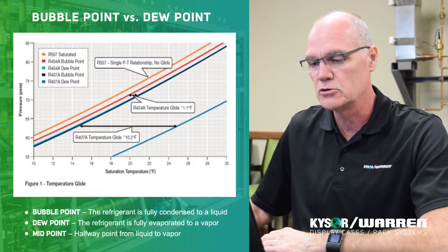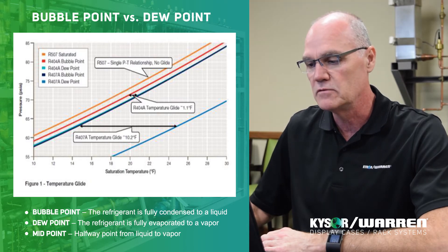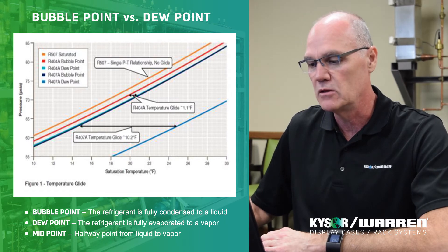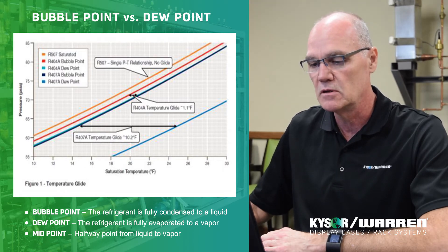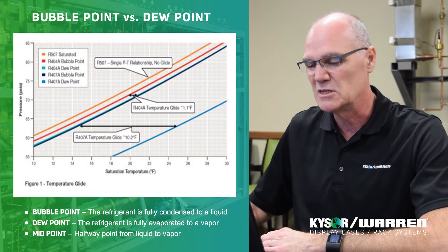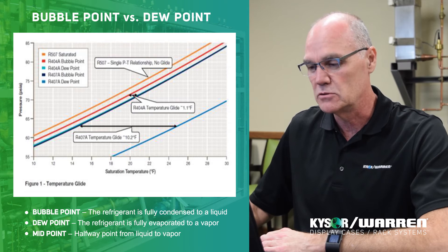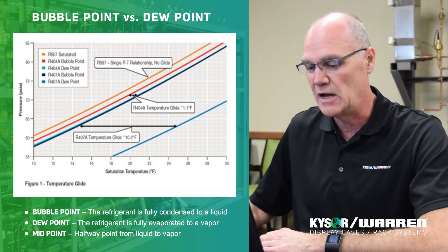If you look at the chart on the screen, the graph shows 507 and 404A, and there's one line that represents each one of those. So if I use 507 for example and I have a temperature of 20 degrees Fahrenheit, that corresponds to a specific pressure of approximately 72 psi. But if you look at a high glide refrigerant, there are two lines, and terms like bubble point, dew point, and midpoint are introduced into the conversation.